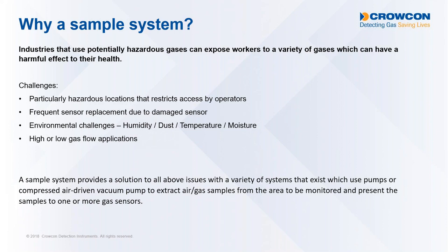So we're able to mount a sample line in that location, and it will draw out that sample to a safe location, which is going to be monitored regularly. So any maintenance or servicing that's done to your gas detection system is done in your safe area, rather than having to send an operator into that particular area.